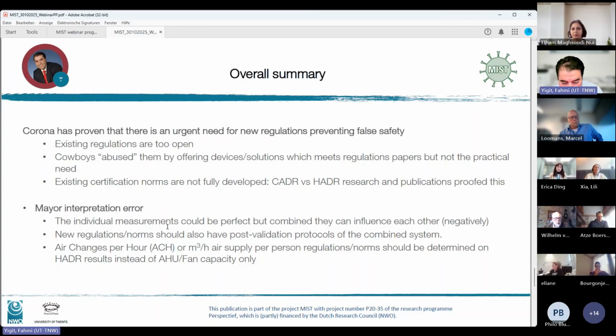For example, in restaurants or offices we claim 30 cubic meters of fresh air per employee. But if these 30 cubic meters don't arrive to the employee, if only 20 arrive, then you don't meet the regulations. So the post validation protocols should target 30 cubic meters, not just the technical protocols.